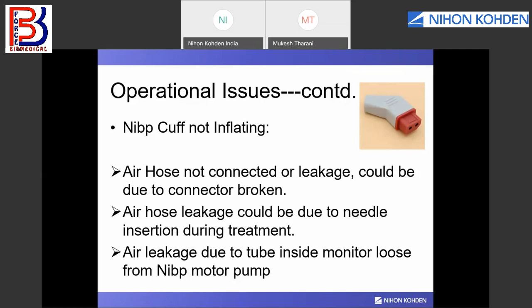The third possibility of air leakage is that the NIBP pump, which you have seen in the previous slide, is connected with the tube and the sensors on the analog board. That tube or sensors may have come out due to high pressure. So you need to open the monitor before going for a secondary check.